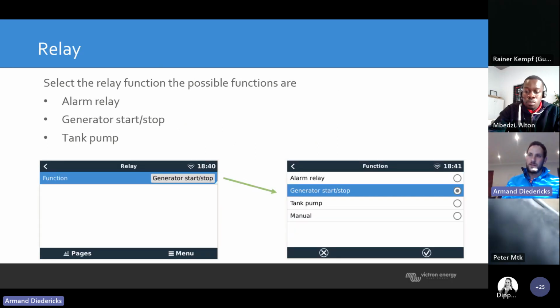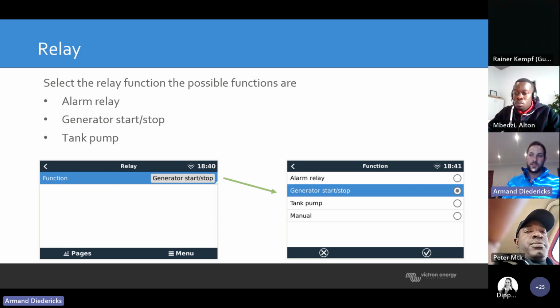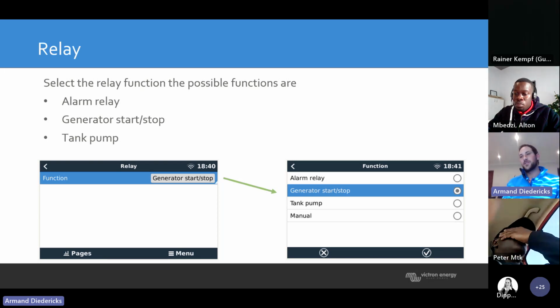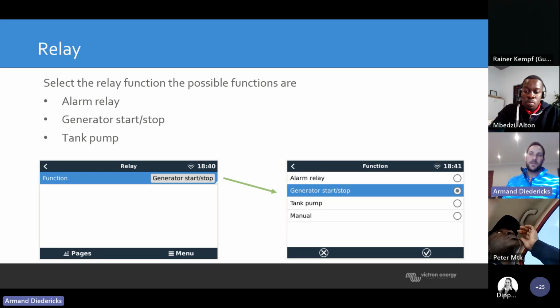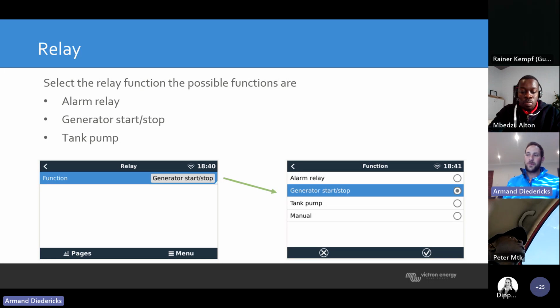Right. So select the relay function. Once you connect the relay, it's a two-wire start-stop function, common, normally open, normally closed, as I mentioned. So you need to actually physically go and program the relay. Select the relay function, and possible functions are alarm relay, generator start-stop function, or tank. So for the start-stop function, you go to function and select generator start-stop, and then if you wire the two wires and make it normally closed to start, you can actually wire the two wires and close it up, and you'll hear the relay switching on the Cerbo.